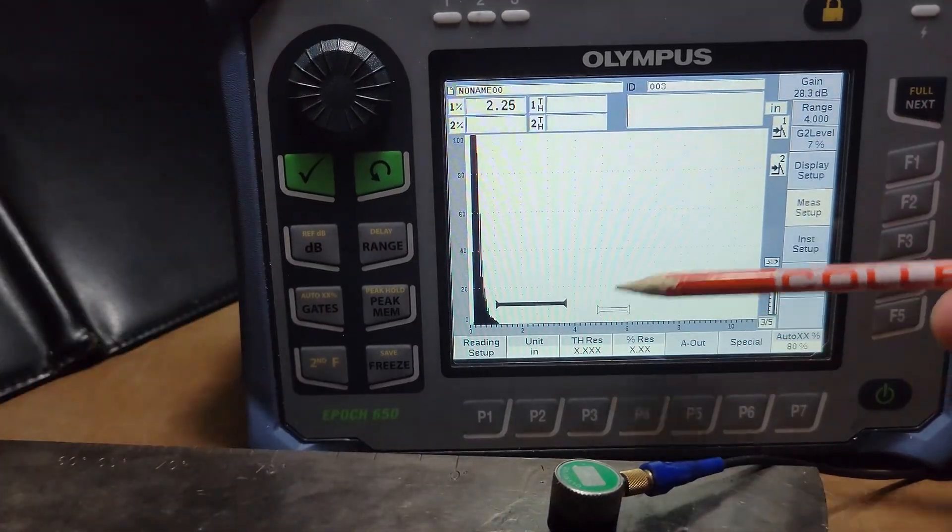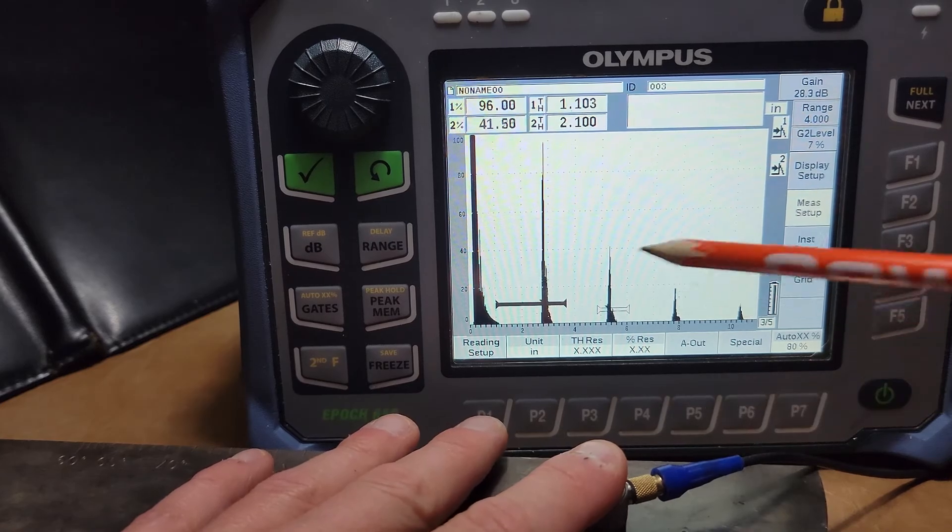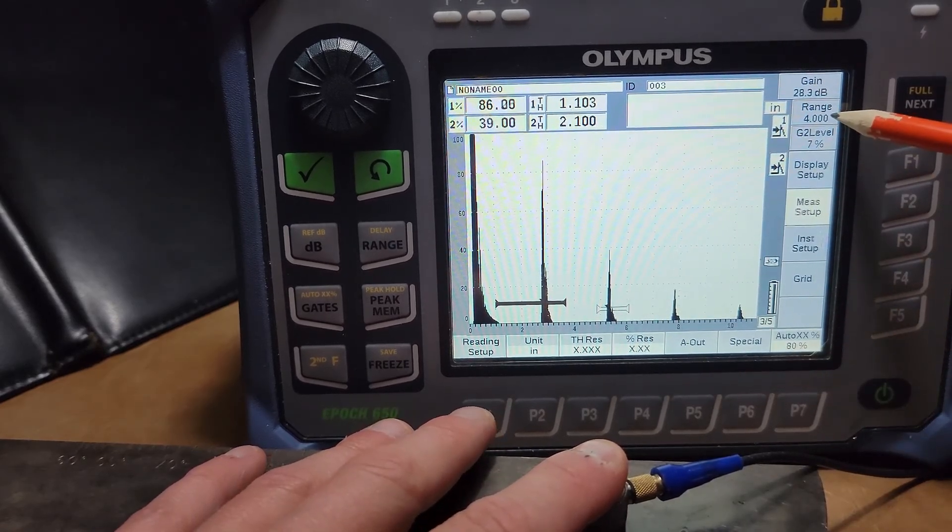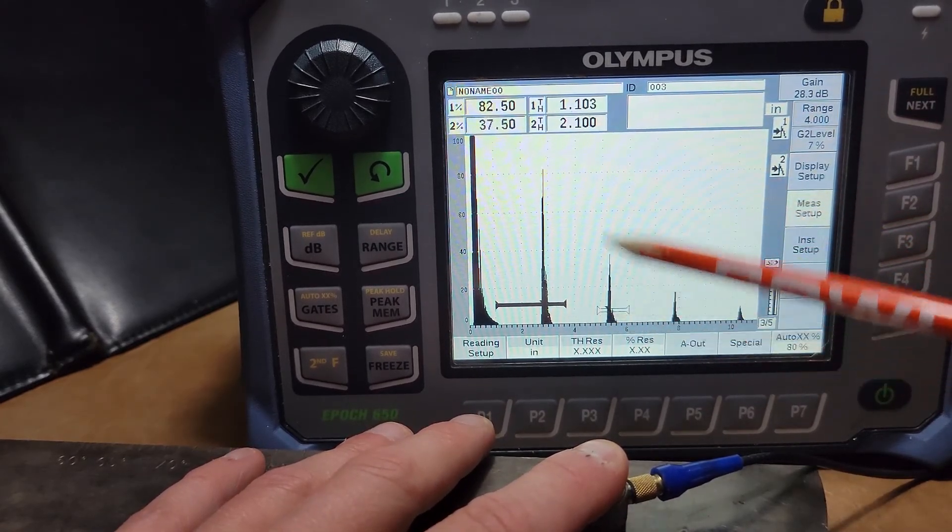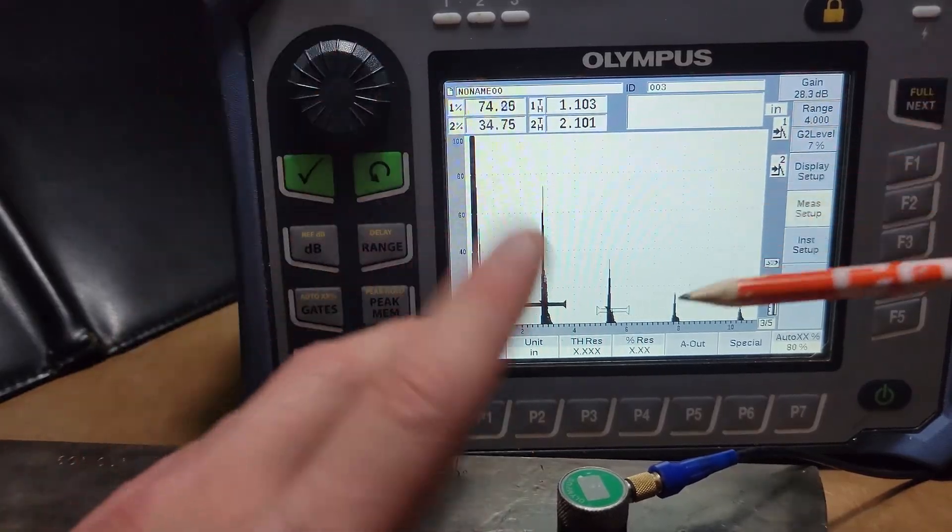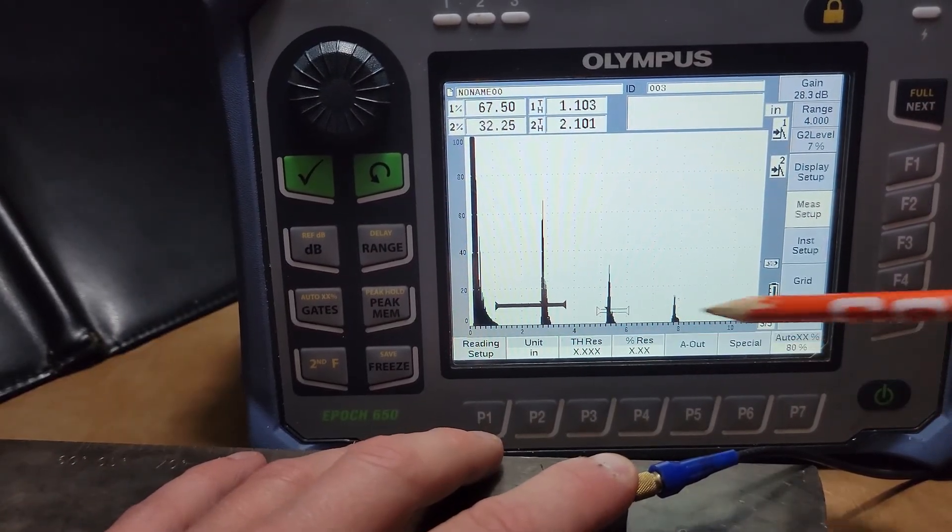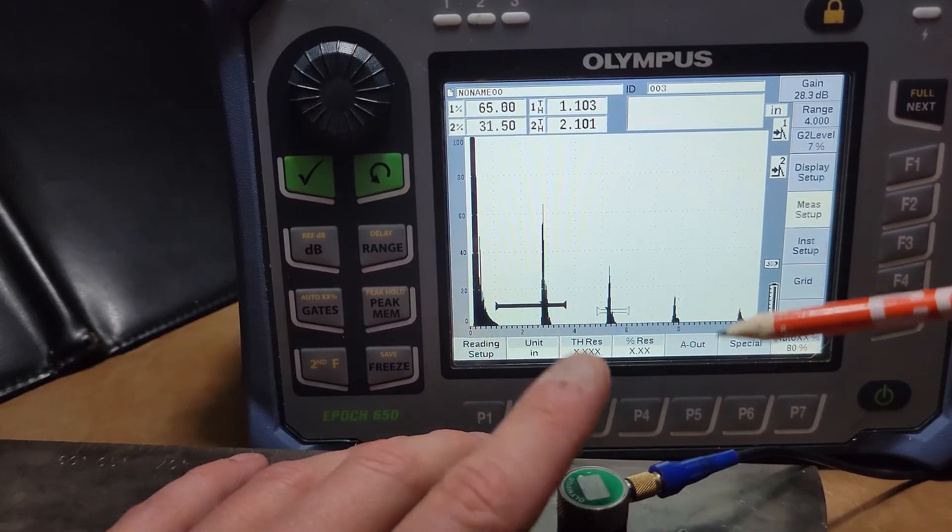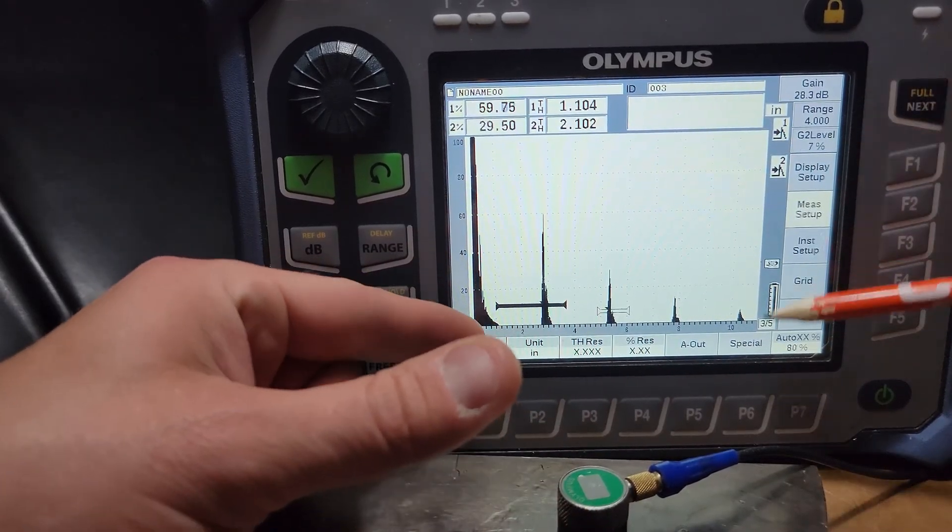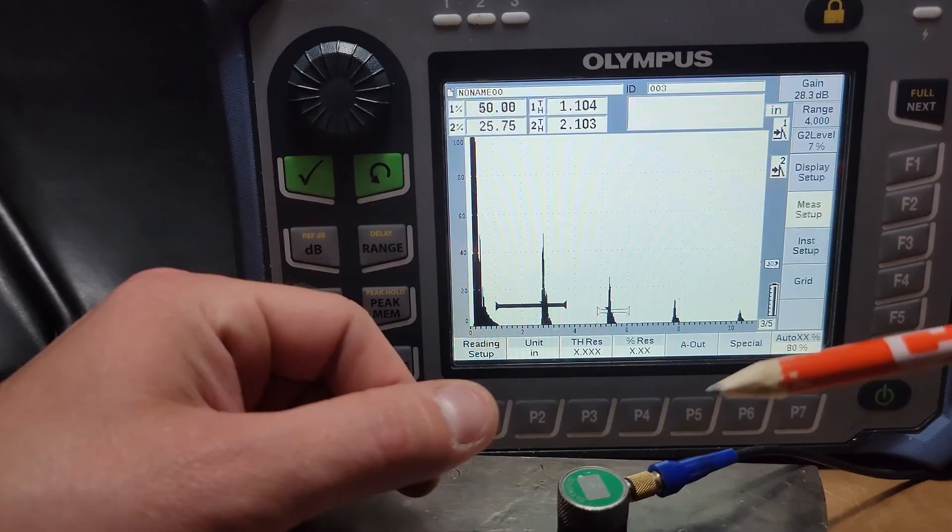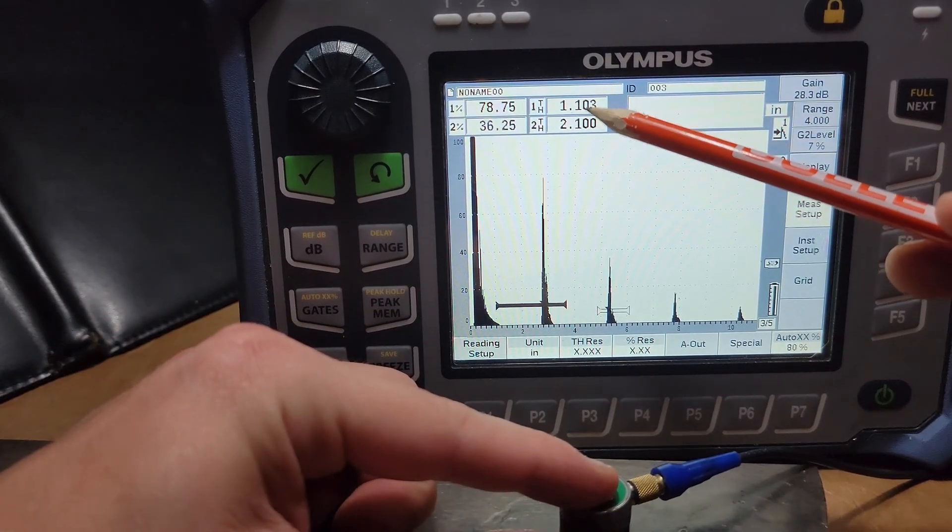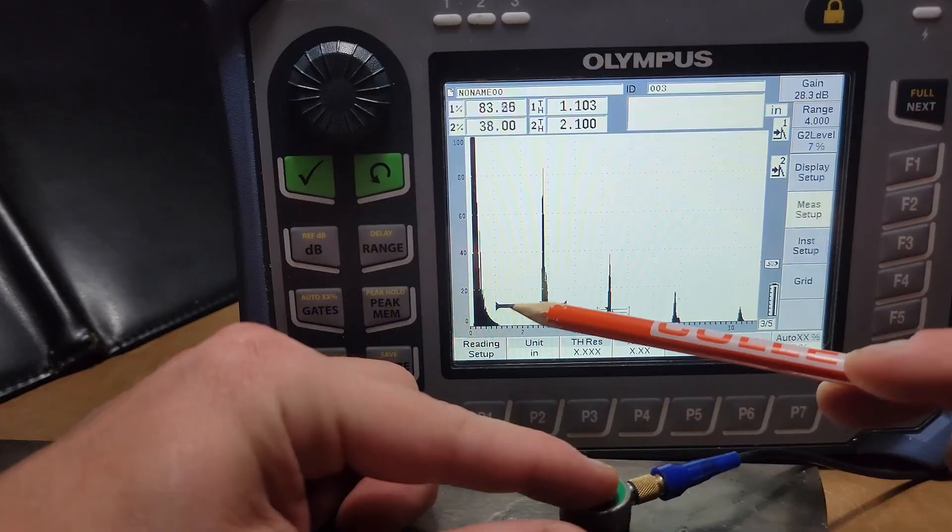Meaning if I'm on a four inch range here, my two inch should be around 50% screen height. And I intuitively know that because I understand how the A scan should present itself based on the range and the percentages, right?